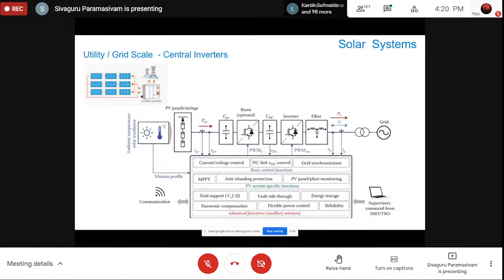But in short, the purpose of MPPT is, imagine that you have a solar panel and there is a cloud passing by, and then the irradiance level falling on the solar panel reduces. So what happens is, the power output of the inverter connected to the grid will always vary with respect to the irradiance level falling on the PV module. So there is an algorithm run on these inverters which will constantly see what is my previously generated power. For example, if it is a 1 megawatt system, it will see, okay, I was generating 600 kilowatt now, and next, what is my generation?